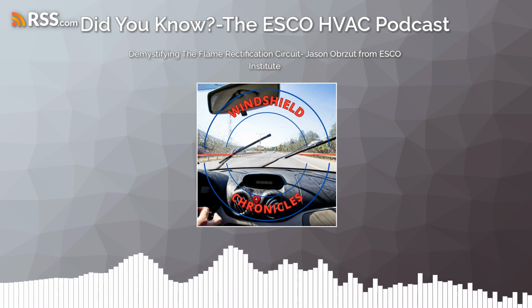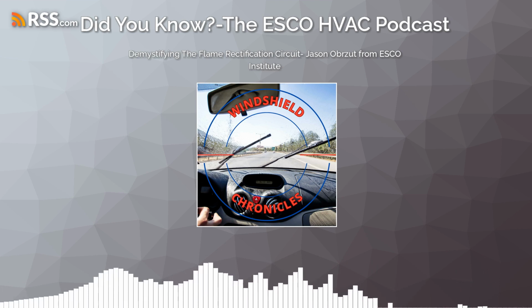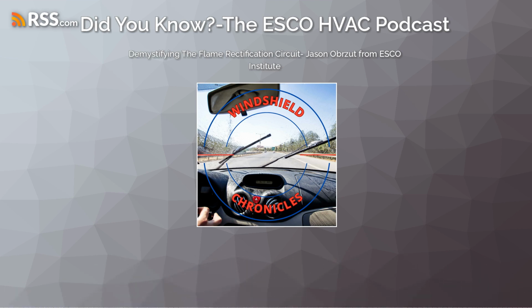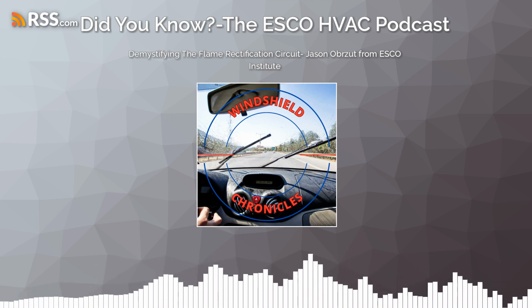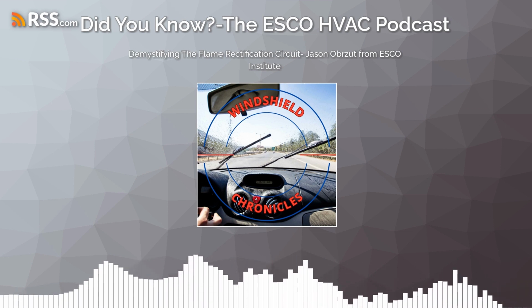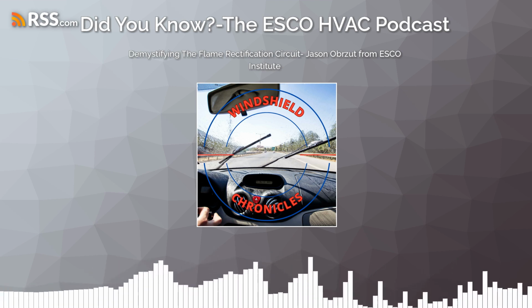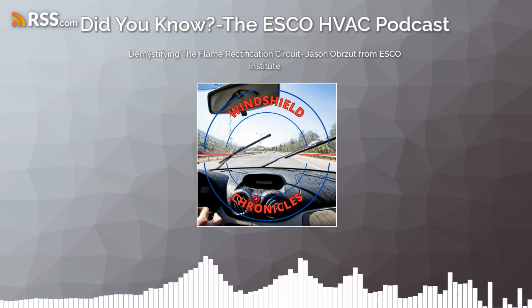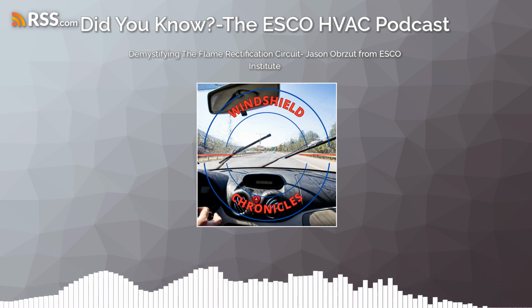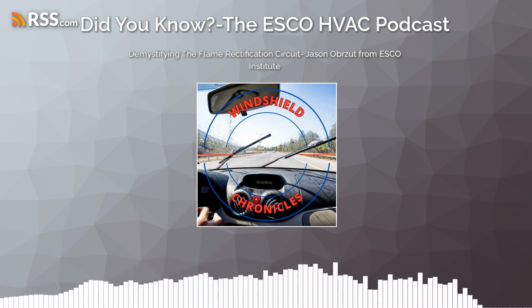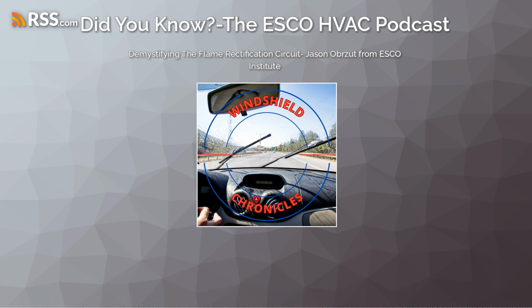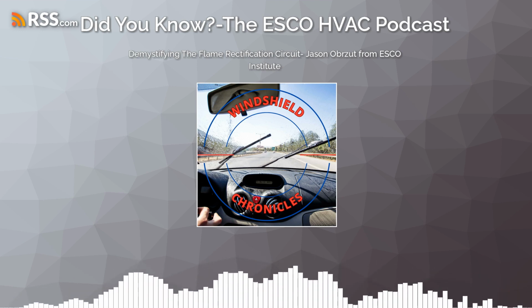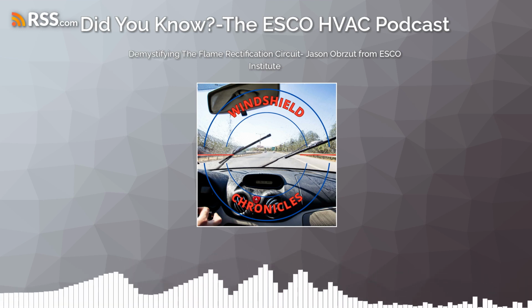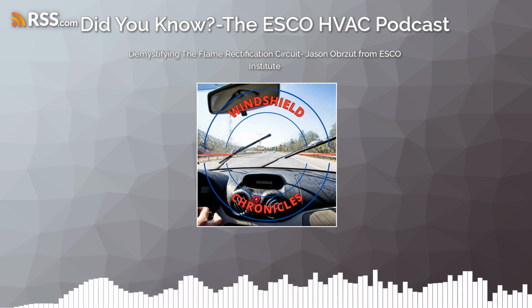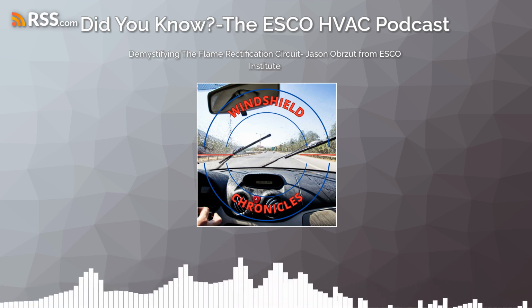Exactly. And we are going to do work with this. When we talk about K-type thermocouples, like for our meters, well, same kind of thing. We're generating a voltage that our meter is going to read and interpret as temperature. Well, that's all fine and dandy when we're talking about thermocouples. And if maybe we need a little bit more, because remember, we're going to do work with this. So on a residential light commercial gas furnace, a water heater, a fireplace, we're going to generate some voltage and we're actually going to do work with that voltage.